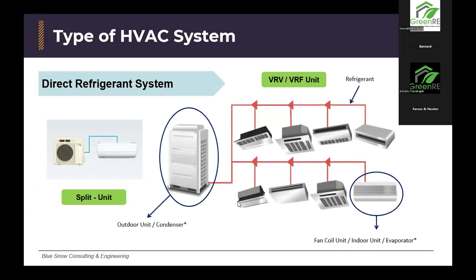Okay, this is one of the HVAC systems, which is the direct refrigerant system. This one is the most commonly used in residential and small offices, the split unit. This is the typical system that we use. And this system mainly only uses refrigerant as its medium of heat transfer. So the next one is the VRV or VRF unit.